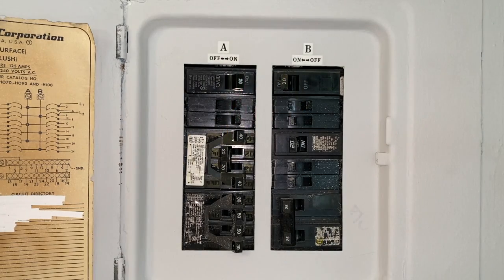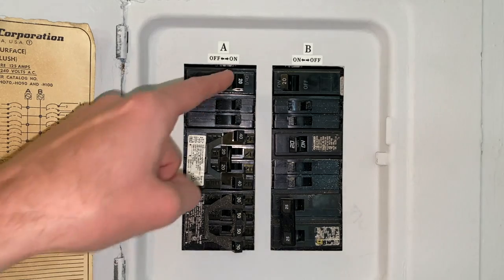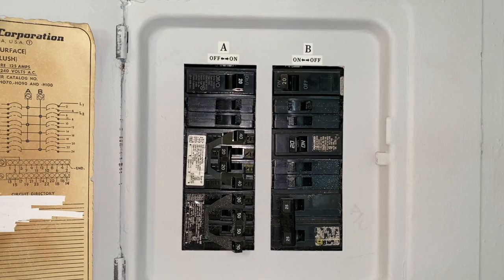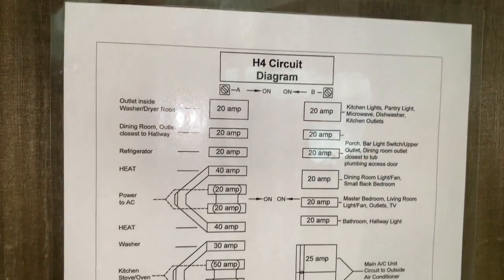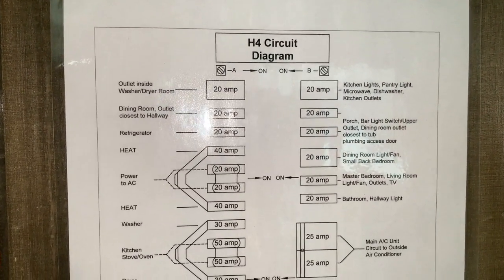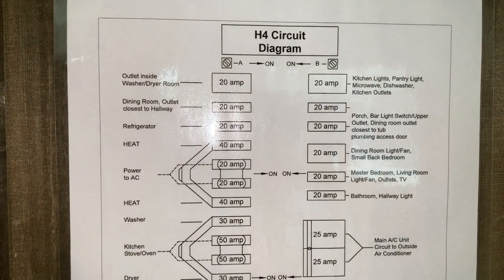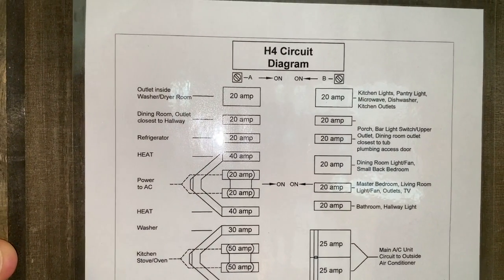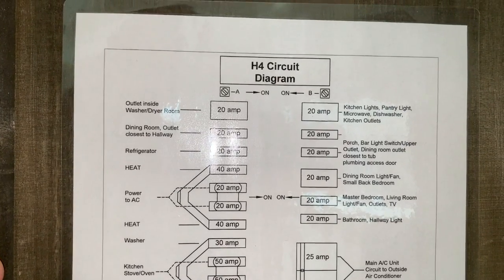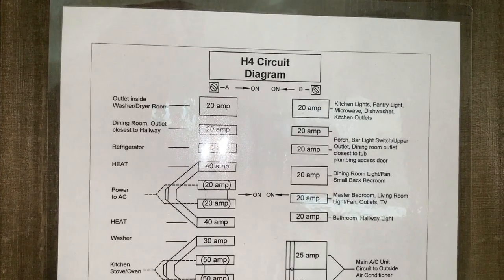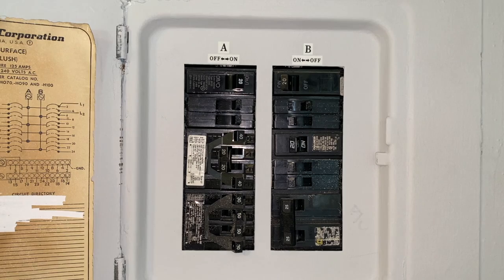I'll set that tool aside. If you experience that or have that setup, it may lead you to believe that these are your main shutoff breakers. However, they are not. Going back to the diagram, upper left and upper right, the 20 amp circuits start on the left-hand side, outlet inside, washer dryer room, and then to the right, kitchen lights, pantry light, microwave, dishwasher, kitchen outlets. Again, those are not your main shutoff breakers, or not ours in this case.